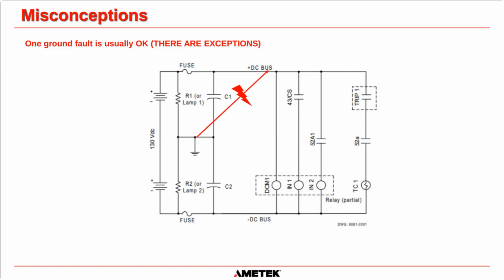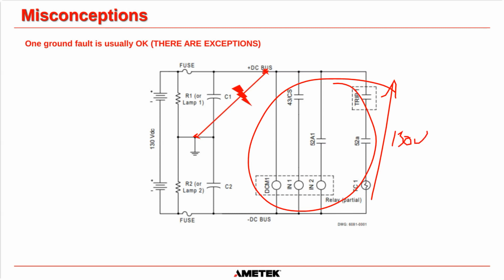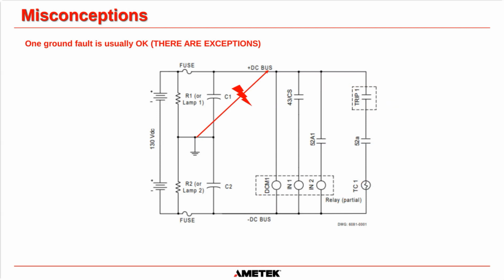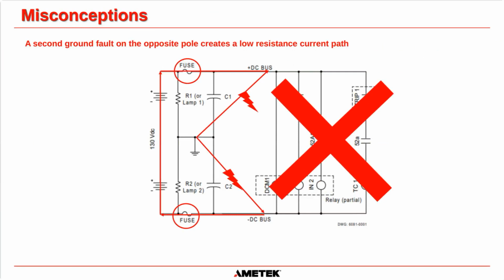So let's say somewhere in the switchgear equipment, we have a fault between the DC bus and ground. All that does is it makes ground now at the same potential as the DC bus. All of this equipment here, all it's looking for is 130 volts. It doesn't care about ground in most circumstances. It couldn't care less that you've got a positive ground fault on. It's going to carry on working regardless. The main issue is if you then get a negative ground fault when you haven't cleared your positive ground fault, okay?